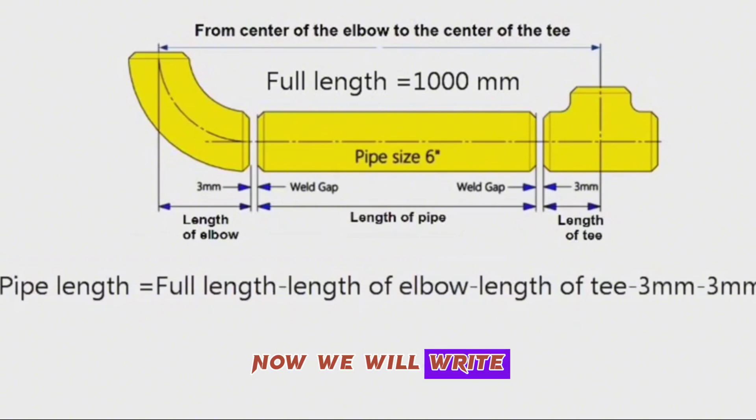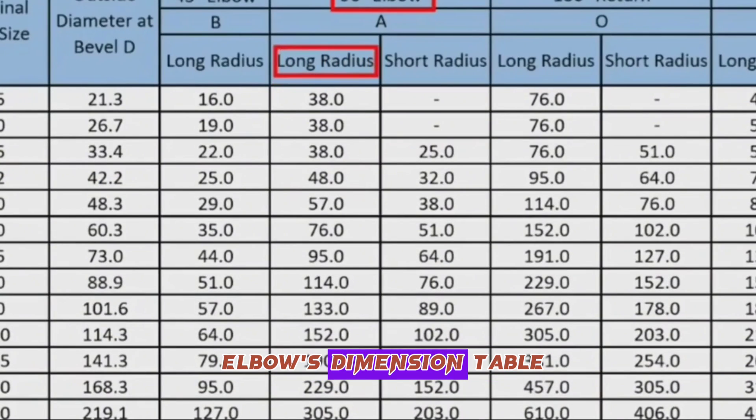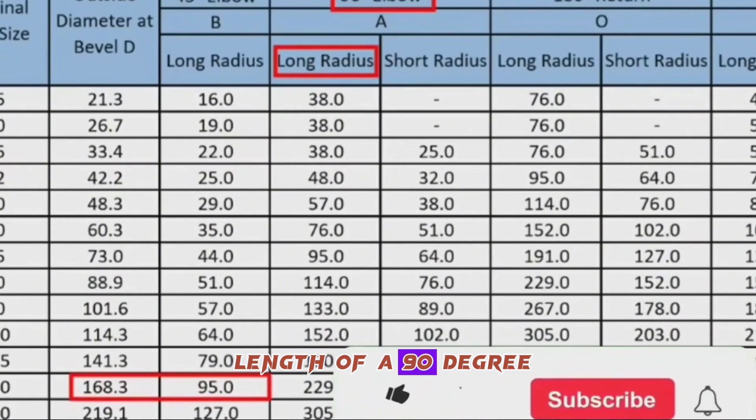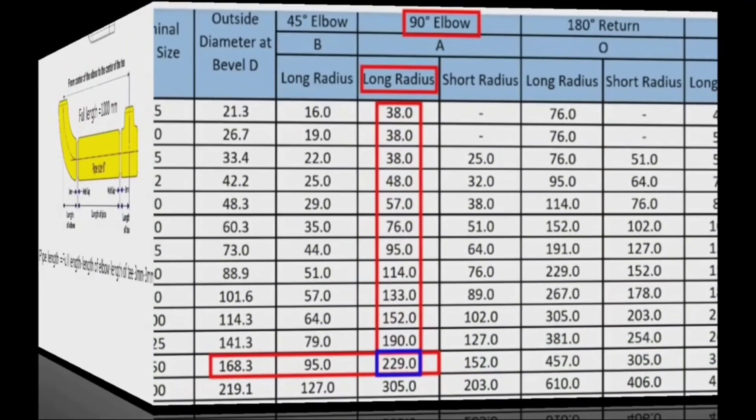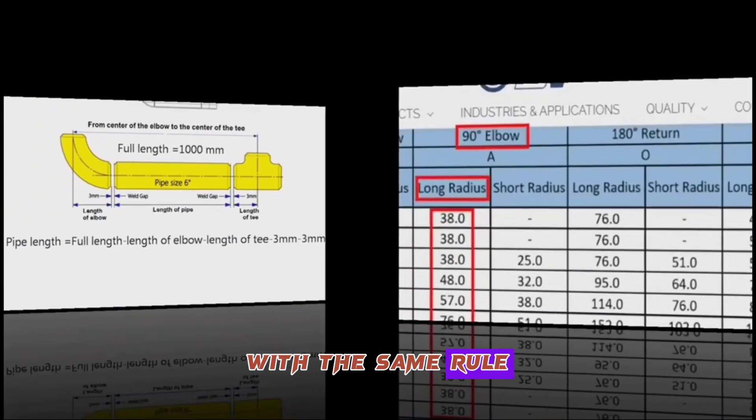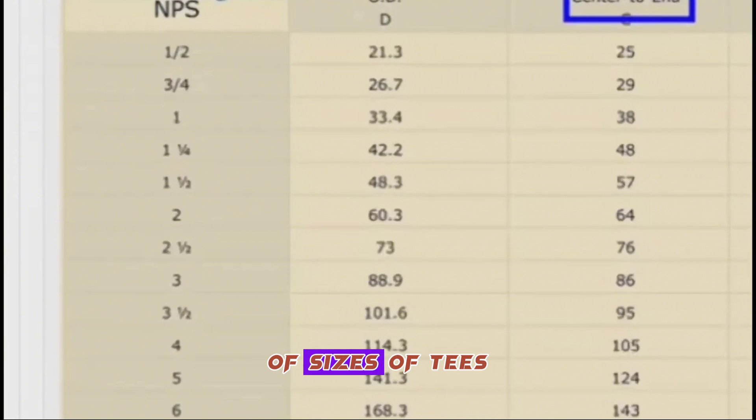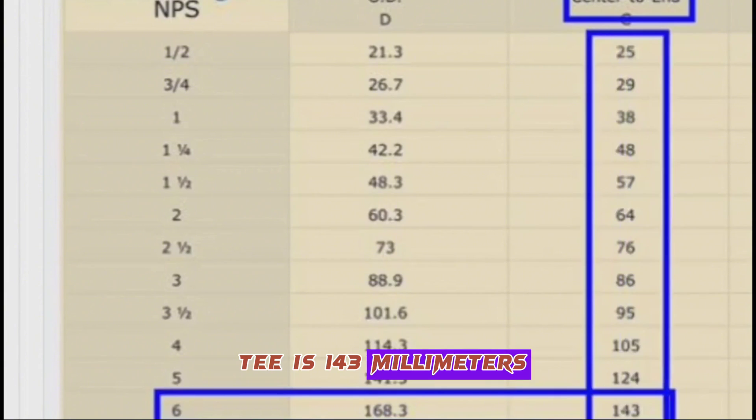Now we will write and calculate the dimensions of the pipe fittings in this pipeline from their standard tables. First, looking at the elbow's dimension table, we find that the length of a 90-degree 6-inch elbow is 229 millimeters. With the same rule, we look at the standard table of sizes of T's and learn that the center to end of a 6-inch T is 143 millimeters.